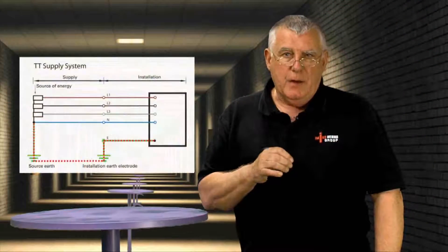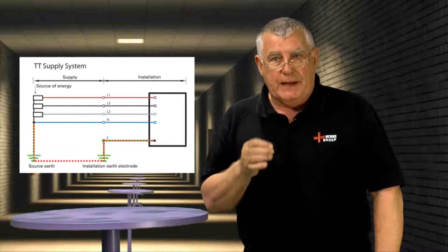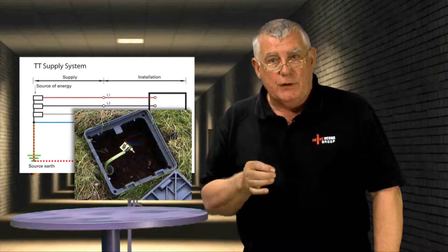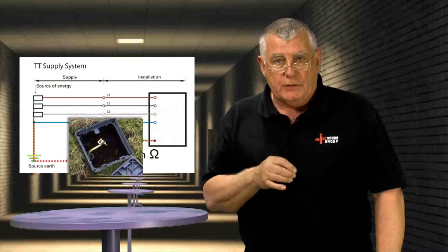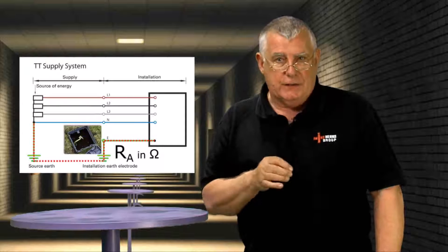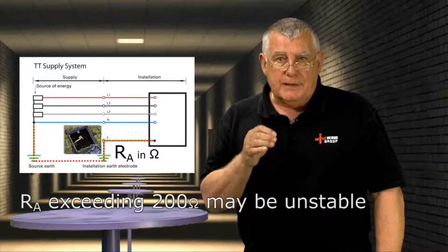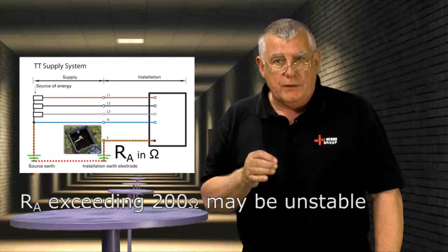With a TT system, part of the earth return path back to the generator or transformer is not provided by a dedicated conductor, but actually through the mass of earth itself. The resistance of an earth electrode, RA, is likely to be much higher than the value of ZE we discussed earlier for a TN system. In fact, the regulations only recommend that the resistance of an earth electrode be as low as practical and that a value exceeding 200 ohms may not be stable. So on a TT system, earth fault currents aren't always going to be of high magnitude, which may mean that the maximum disconnection times may not be achievable using protective devices such as fuses or circuit breakers.